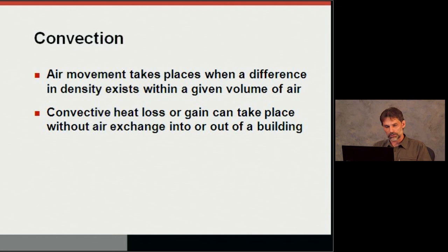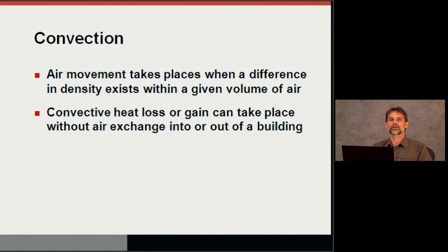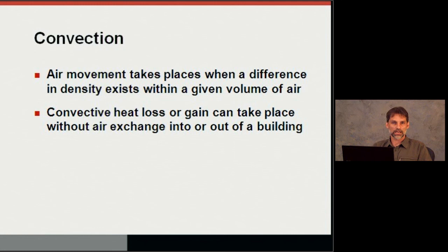Convection is the third way we discuss heat movement in and out of our buildings. It's really air movement that takes place when a difference in density or temperature exists. The warmer the temperature, the lighter and less dense the air; the colder, the more dense. Near a window, air passes through and cools off, becomes dense, and pools down where a child might be playing or where your feet are — creating cold feet. That convective loop drives heat loss: warm air rises, comes into contact with a wall or window, and sets up a pattern that aggravates heat loss.